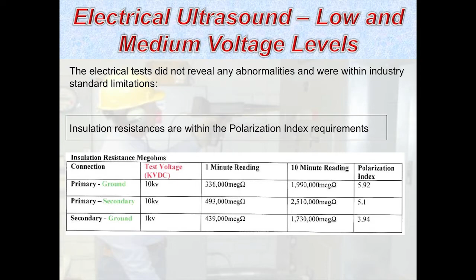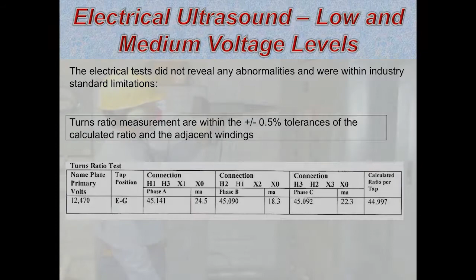The turns ratio measurements. Remember I said this looks for turn-to-turn shorts. It's the only test that can tell us that. You may or may not get some indications that it's occurring with an infrared camera or an ultra probe, but you can never be sure unless you run this test. The tolerances on this are 0.5%. So when you apply this test, you calculate what the ideal ratio should be and gauge the results against that, plus each measurement on each coil. And they all have to be within 1/2 of 1%. So the tolerances are very tight for a reason of the voltage and current balance I mentioned earlier. This was right on, so no damage there.